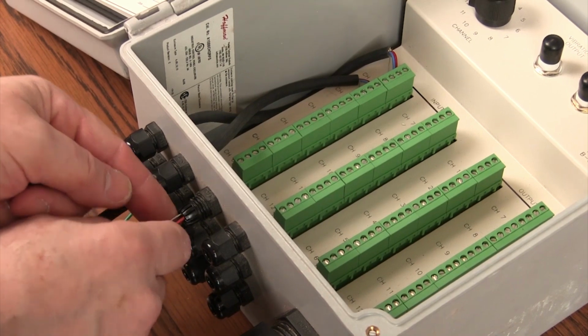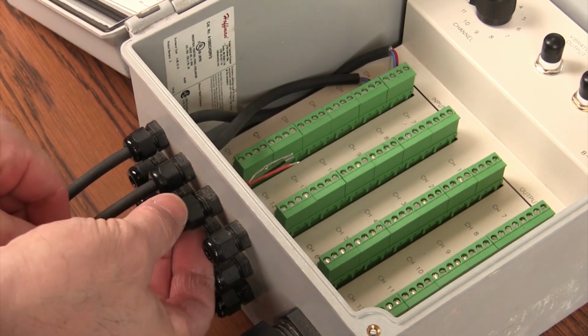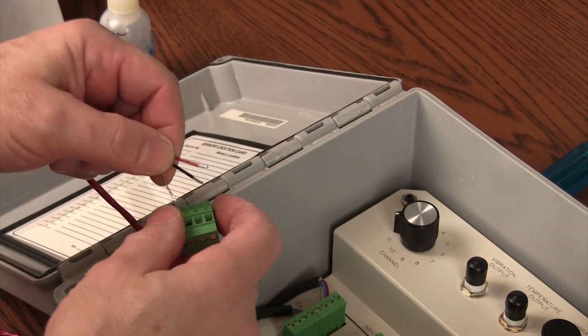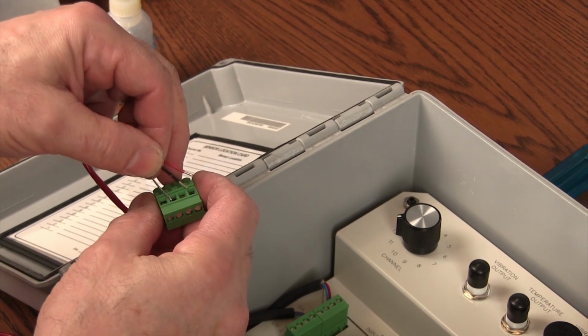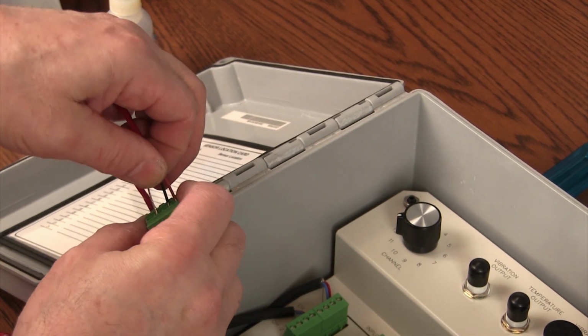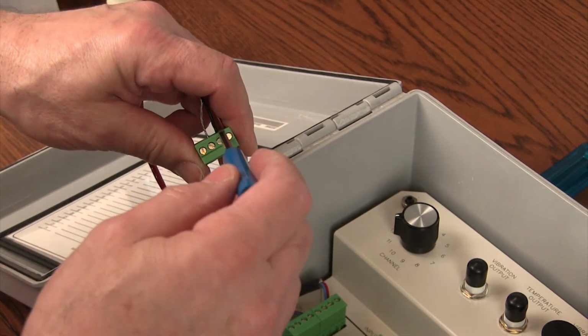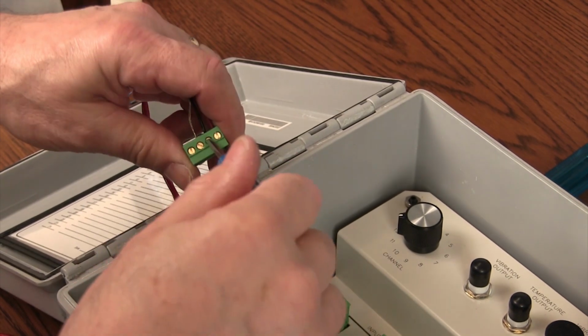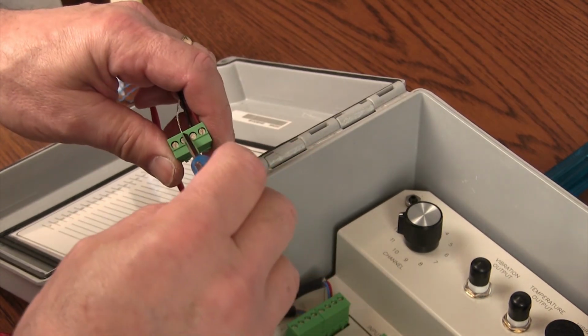Finally, we're using the red Teflon jacketed cable on channel 3. The only difference here is the black conductor is accelerometer ground, red is still signal, and we will still connect the drain wire from the foil shield.